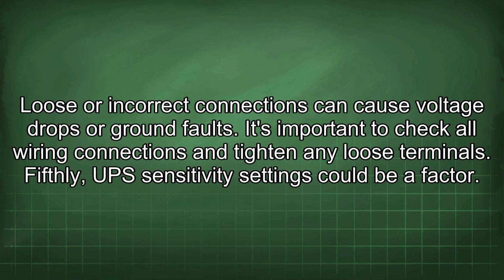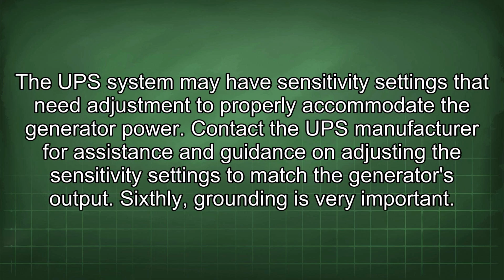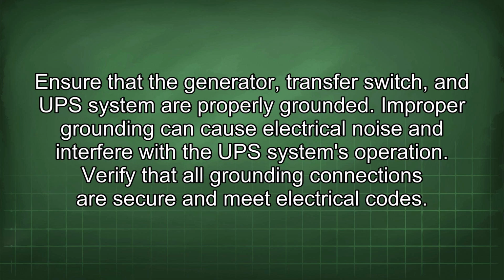Fifthly, UPS sensitivity settings could be a factor. The UPS system may have sensitivity settings that need adjustment to properly accommodate the generator power. Contact the UPS manufacturer for assistance and guidance on adjusting the sensitivity settings to match the generator's output. Sixthly, grounding is very important. Ensure that the generator, transfer switch, and UPS system are properly grounded. Improper grounding can cause electrical noise and interfere with the UPS system's operation. Verify that all grounding connections are secure and meet electrical codes.